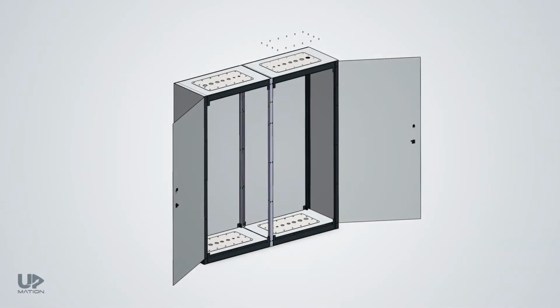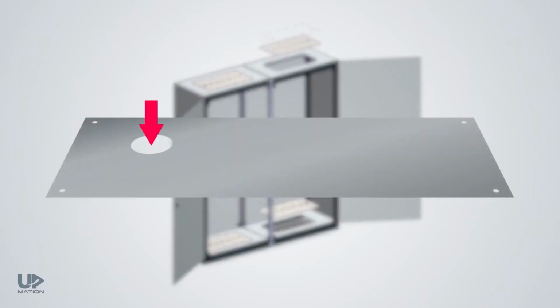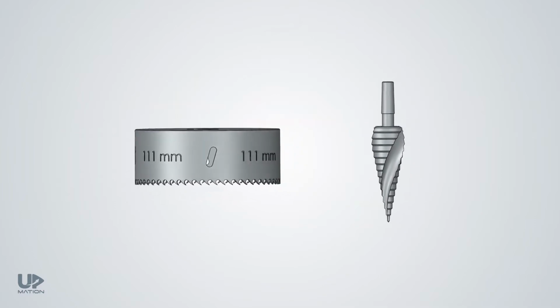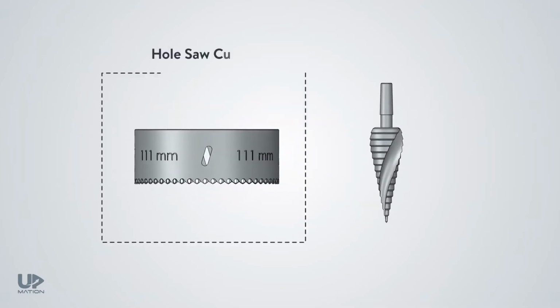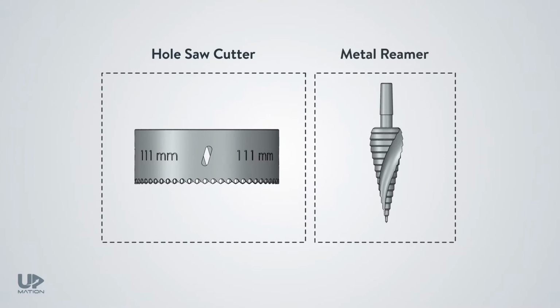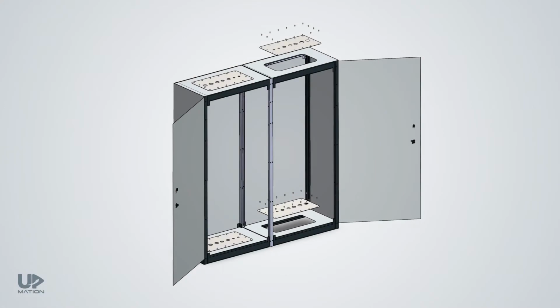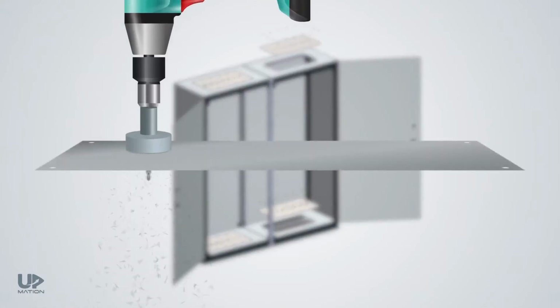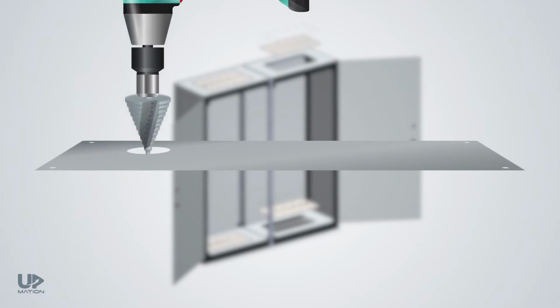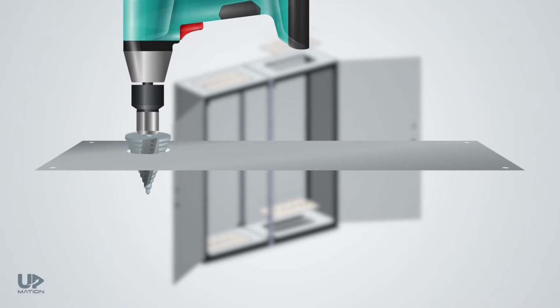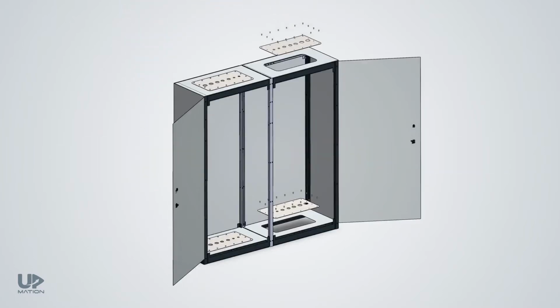What is a gland plate? A gland plate is a detachable metal sheet on top or on the bottom of the panel that is a part of the enclosure. We should drill the gland plate to bring the cables inside the panel. To drill a clean and polished hole on the gland plate, we need appropriate tools like hole saw cutters for steel or stainless steel plates. We also need a metal reamer to polish the edges and to further adjust the size of the hole. So first I drill the hole using the hole saw cutter. Then, as I mentioned, I use the reamer to have a clean and polished hole. After I drilled all of the cable holes that I need on the gland plate, I should reinstall and fasten its screws.